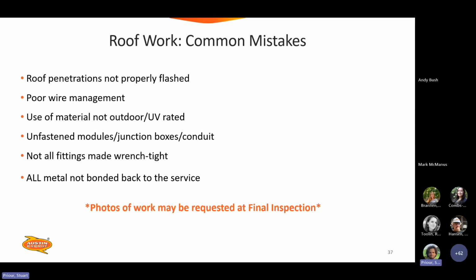If you have unfastened modules, junction boxes, or conduit on the roof. We don't always get on the roof. Occasionally we do, and we find these things. So I know in the summer it gets hot and you're moving quickly because it's uncomfortable, but fastening down all your modules and your junction boxes and your conduit is very important. Not all your fittings are made wrench tight. Also something that takes a little more time, but is essential for the lifelong production of your system.